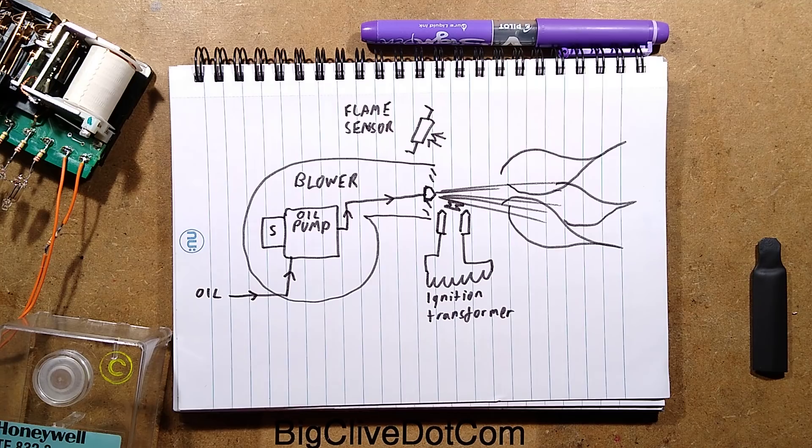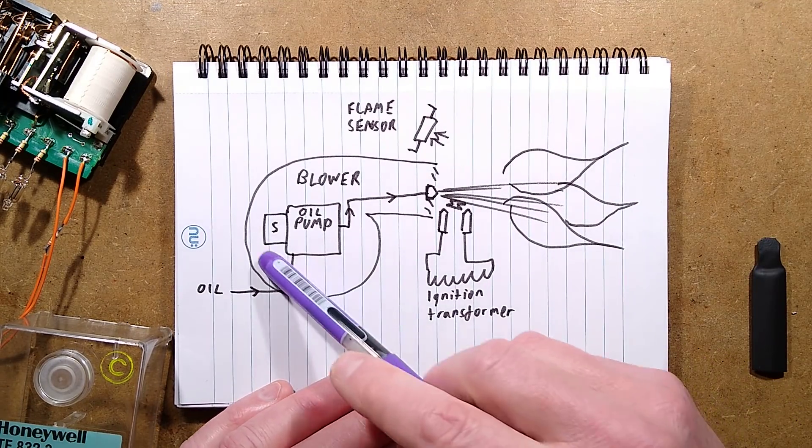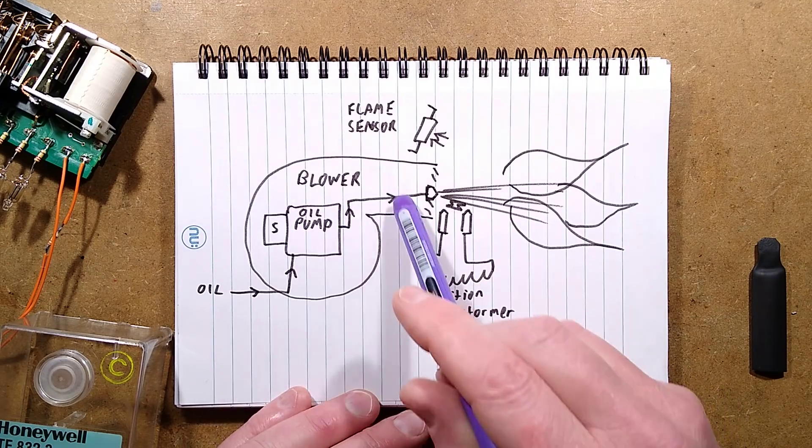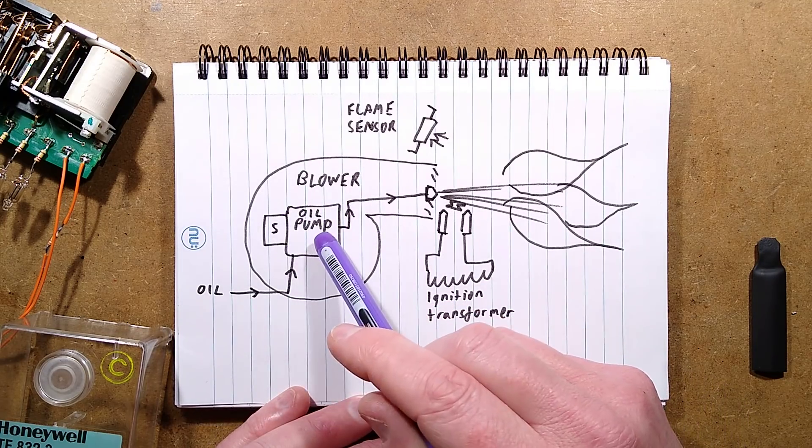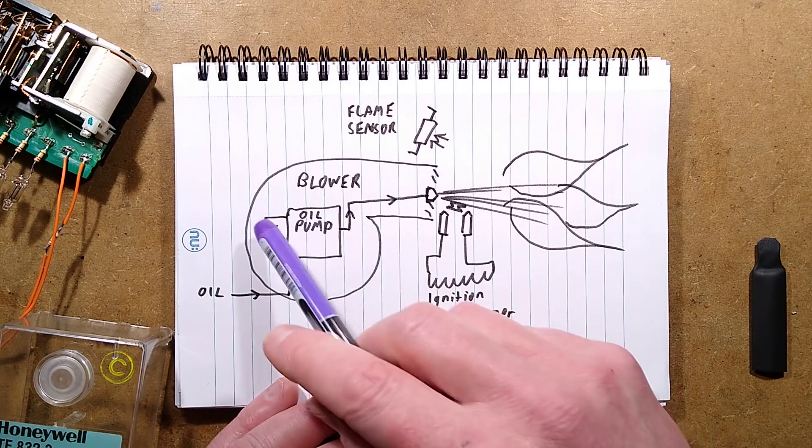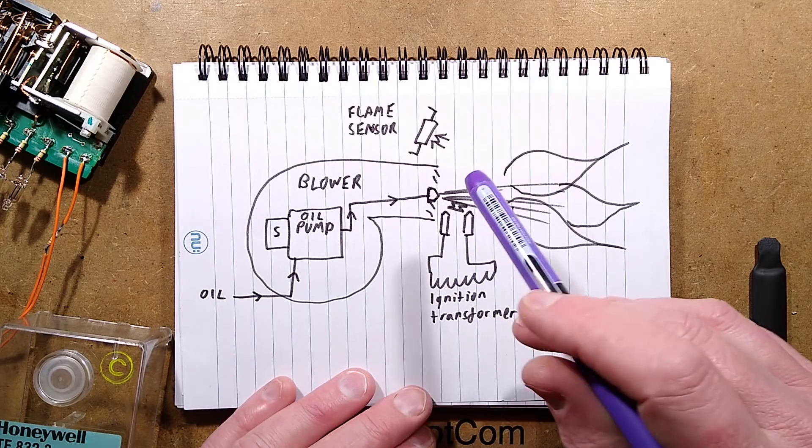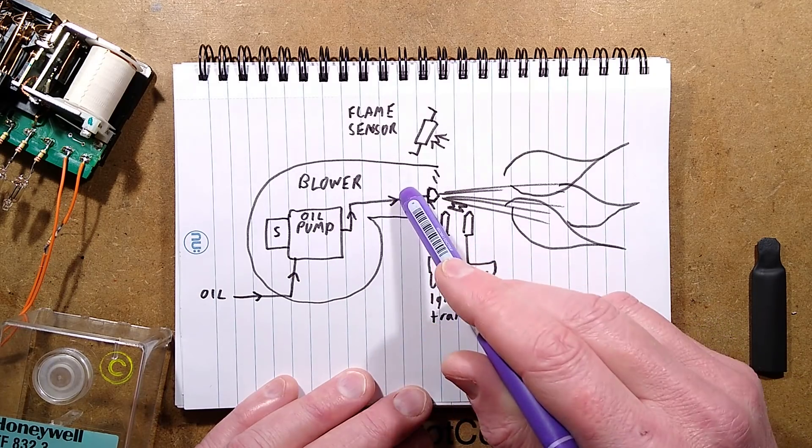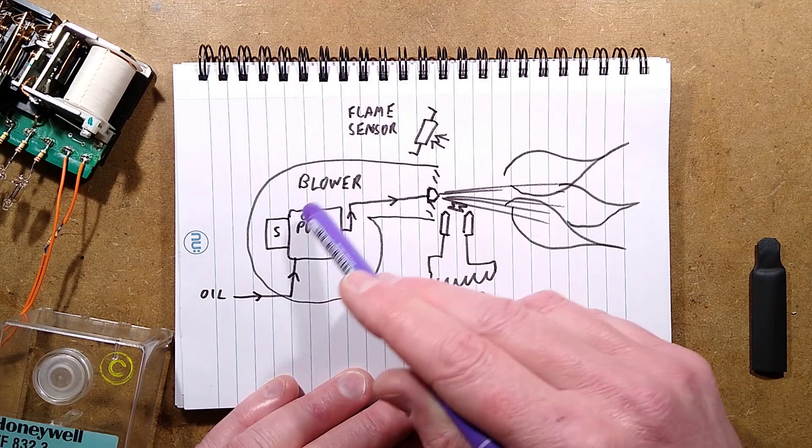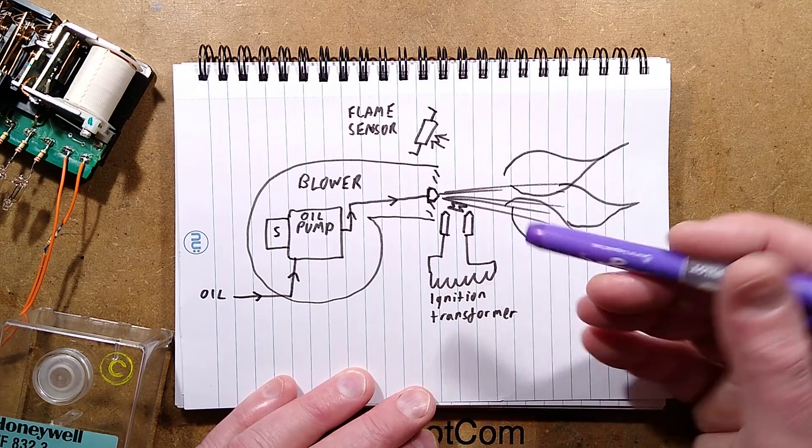But let's take a look initially at how the boiler ignition system is supposed to operate. A typical oil burner has a blower, and on the same shaft is usually an oil pump with a solenoid valve on it. Because that means that although the blower is running, it doesn't necessarily mean it is actually pumping oil out.